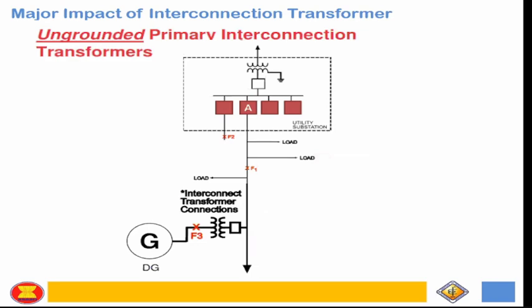Okay? So let's simulate the ungrounded primary interconnection transformer. Ano ba yung magiging scenario? Okay? So this transformer is the substation transformer, distribution substation transformer. Okay? And it has 4 feeders, then in which the distributed generator is being connected to breaker A. Okay? That's the scheme. And then if your interconnection transformer is delta-delta, okay, ungrounded siya, and then Y grounded-delta, still ungrounded yung primary, and then delta-Y ungrounded primary. So those are the ungrounded primary interconnection.